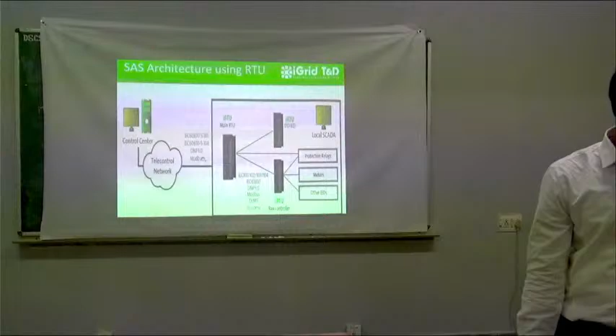It is similar to what we are doing. There are multiple RTUs. Okay, I'll just brief you now. In utilities like Karnataka, they have standardized that the RTU panels should be like this, irrespective of the substations. Say, for example, in Karnataka, we give an RTU panel which has 144 DIs, 80 DOs, that is, they require 80 digital outputs, and 24 analog inputs. Based on that, we select the different modules of our RTU products and we configure our RTU panel.